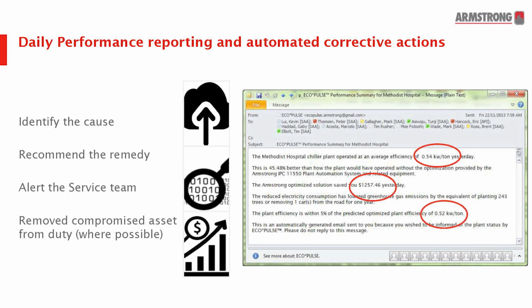We're also able to predict the performance and measure it against the commitments made for that facility. So on a daily basis, the operator gets an email that tells them how well that plant performed yesterday, how well it should have performed based on our equipment performance maps, and if it gets outside a tolerance of 3 to 5% of that predicted performance, we work on what the remedy is to get it back on track.